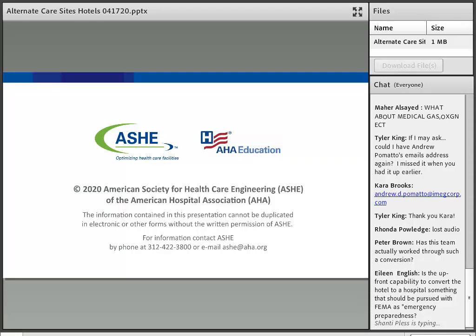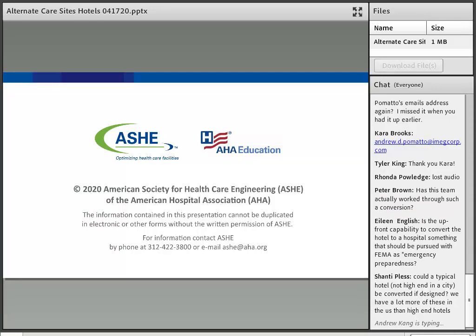Yeah, this is Mike, and I think that's the whole parameter of this thought with this alternate care site. These are for the low acuity type patients, and that would allow the sickest of the sick to stay within the main hospital, where all of the services and infrastructure required for that type of high-level acuity patient would be available, from the airborne infection isolation room, to the medical gas, to the life safety items associated with it. That would probably be the intent. We did look at what it would take to convert a hotel room, a hotel floor, to negative pressure or isolation, and that really comes down to the cost and the speed of construction. Stan alluded to this: who's going to pay for this, and what is that process? It can get really expensive really fast if you look at converting the hotel rooms to airborne infection isolation rooms.